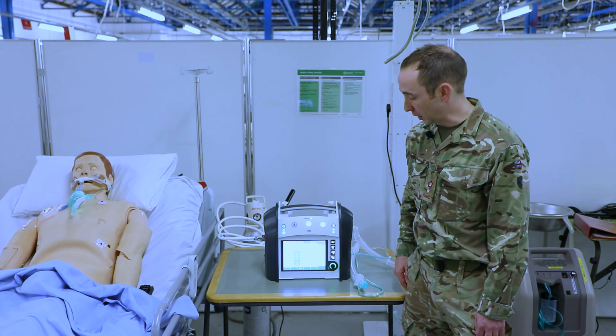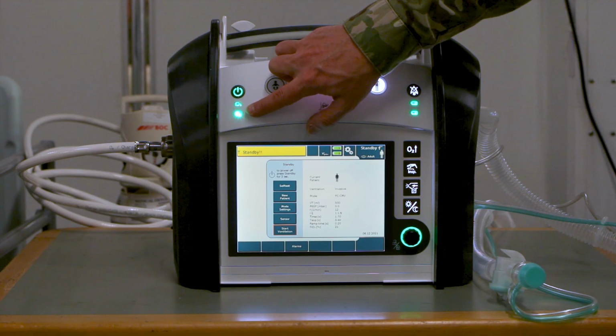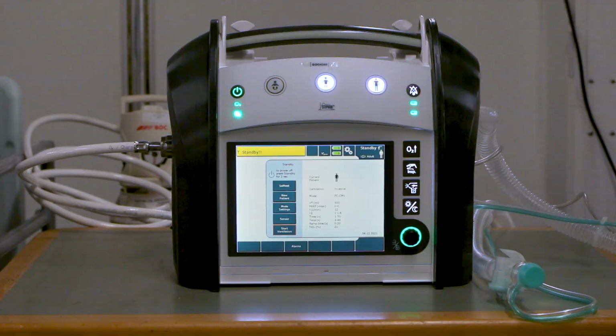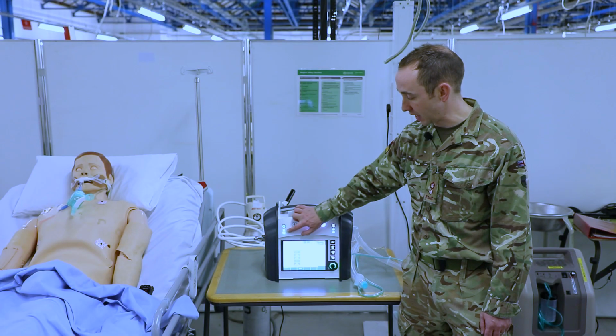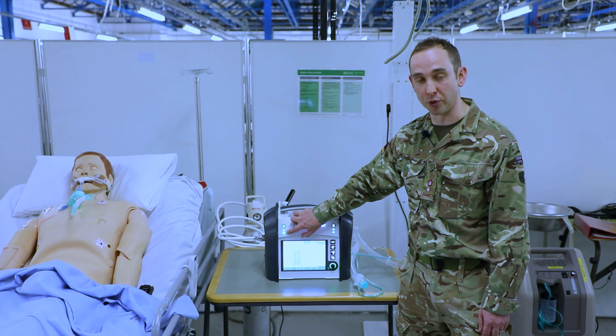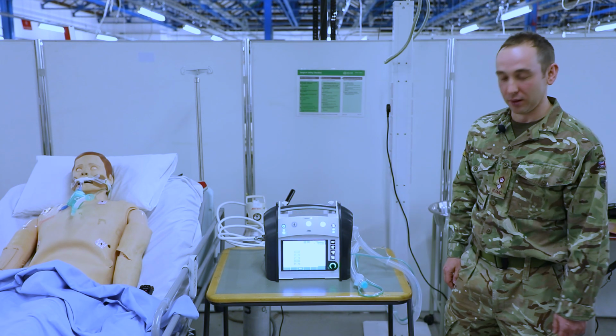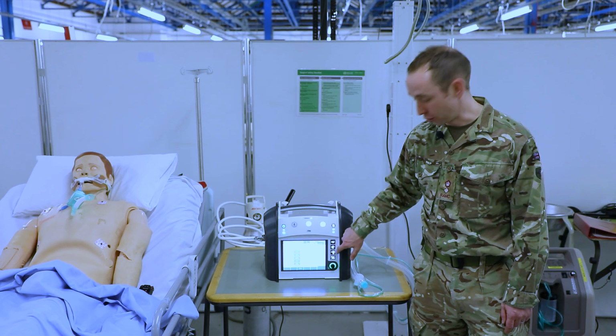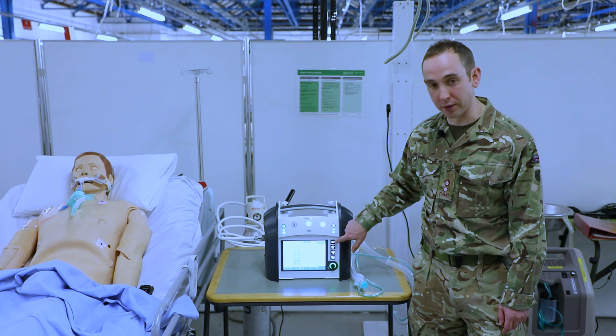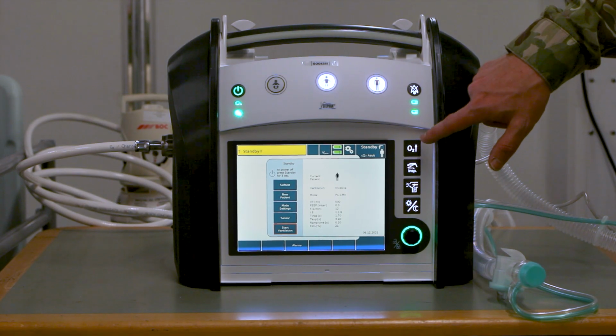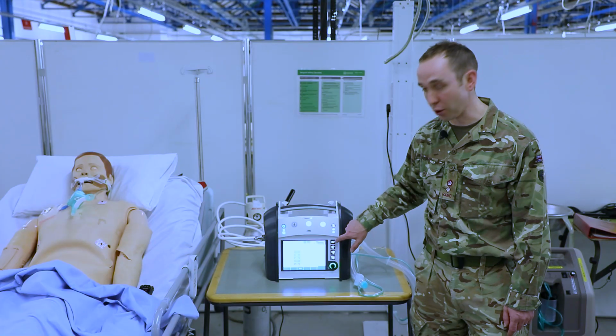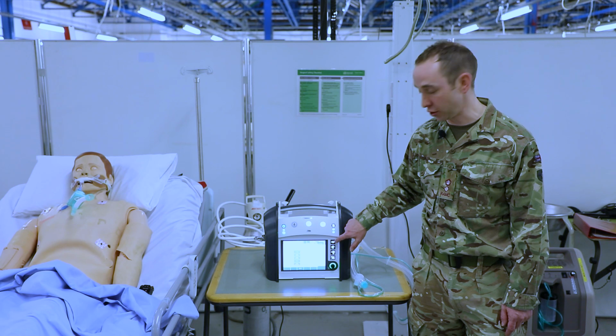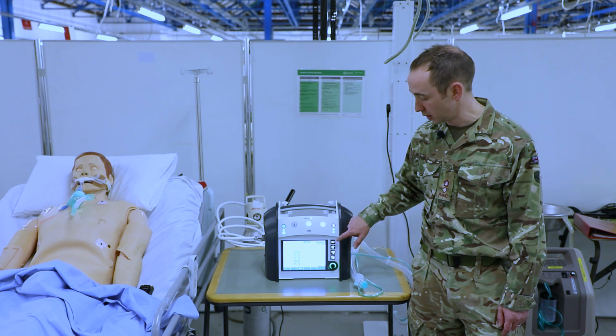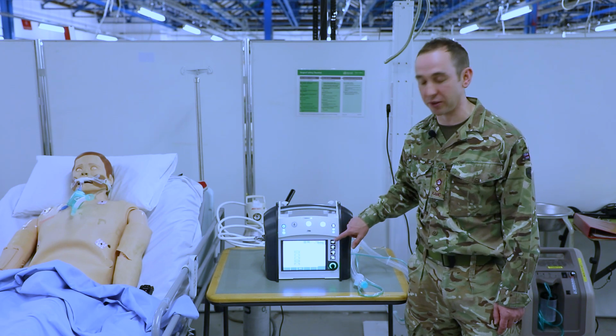Now the ventilator has completed its self-test, you will also notice here that the oxygen, which is now also connected to high pressure oxygen, is now turned green. It will only do this once it's completed its self-test. So we'll now go through the fast-acting buttons on the right side. So the first button is the oxygen flush button. This can be preset in the settings, but can do up to a flush of 100% oxygen if connected to high pressure oxygen, and this can do it for a maximum of 3 minutes.